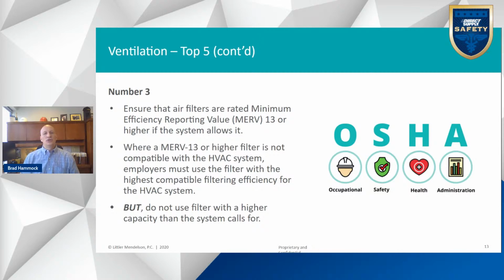One interesting thing OSHA notes in the preamble to the rule is you really need to look at your system specs. OSHA cautions employers not to use a high efficiency filter that's too high for your system, because that can impair the functionality of the HVAC system generally and have a detrimental effect on its efficiency and productivity. That's not OSHA's intent. OSHA's intent is to just maximize it to the design of your system.